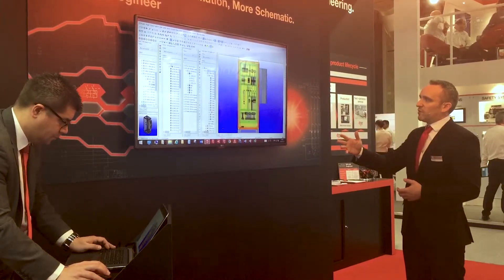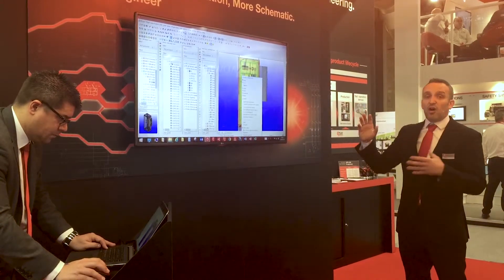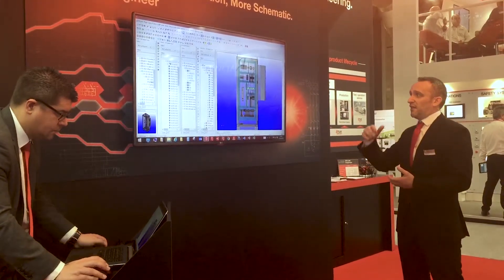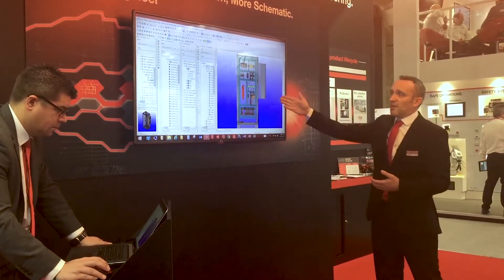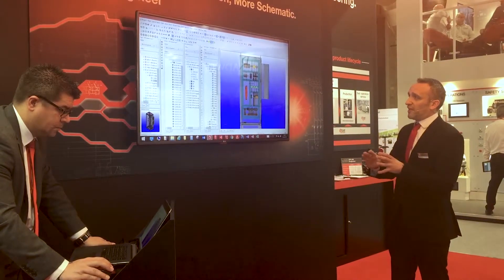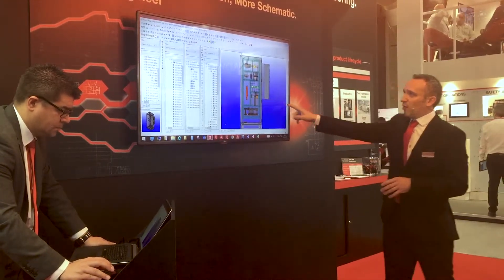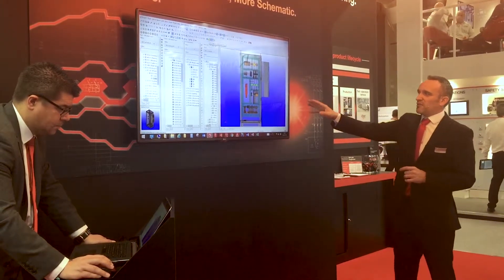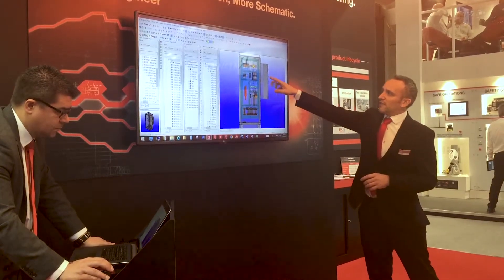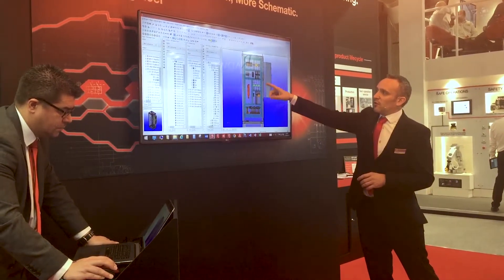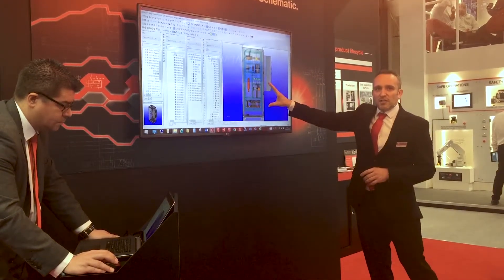What we can do now is drop the high-speed drive in there — it's what we call a hot component, generating a certain amount of power output. We can come back and have a look at our cooling unit here and make sure it's providing enough cooling for the panel. As you can see, it's toggling between orange and red — we've got a hot device there. Our optimal cooling shown in blue is just barely reaching it, so we might want to consider dropping the cooling unit down.